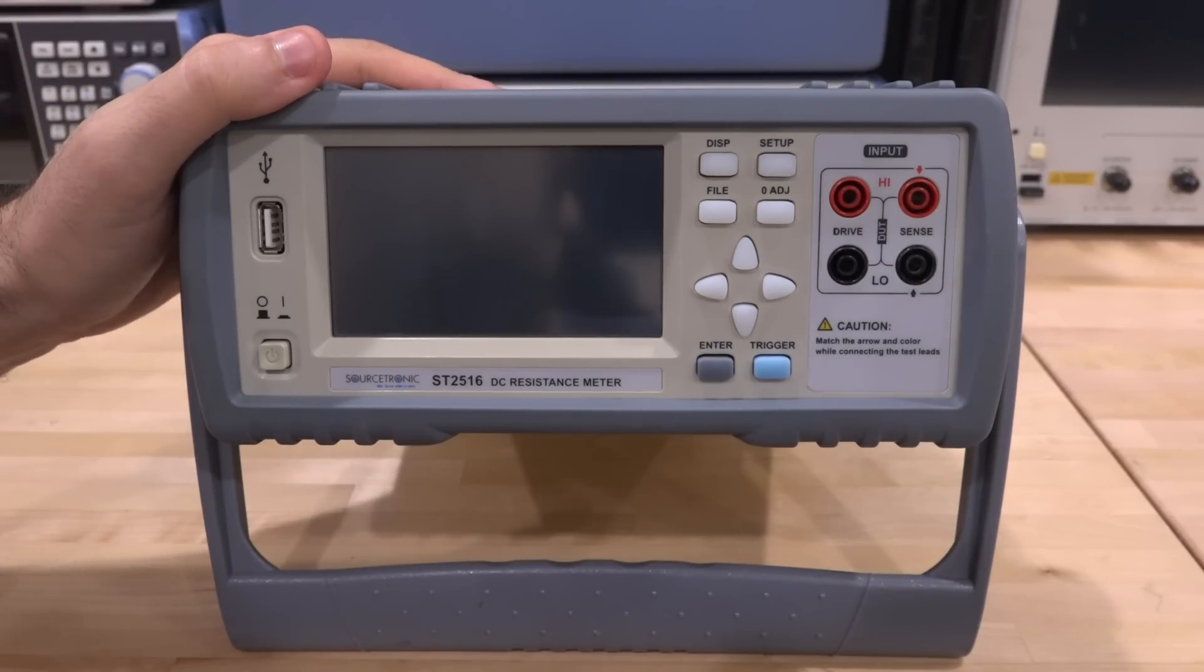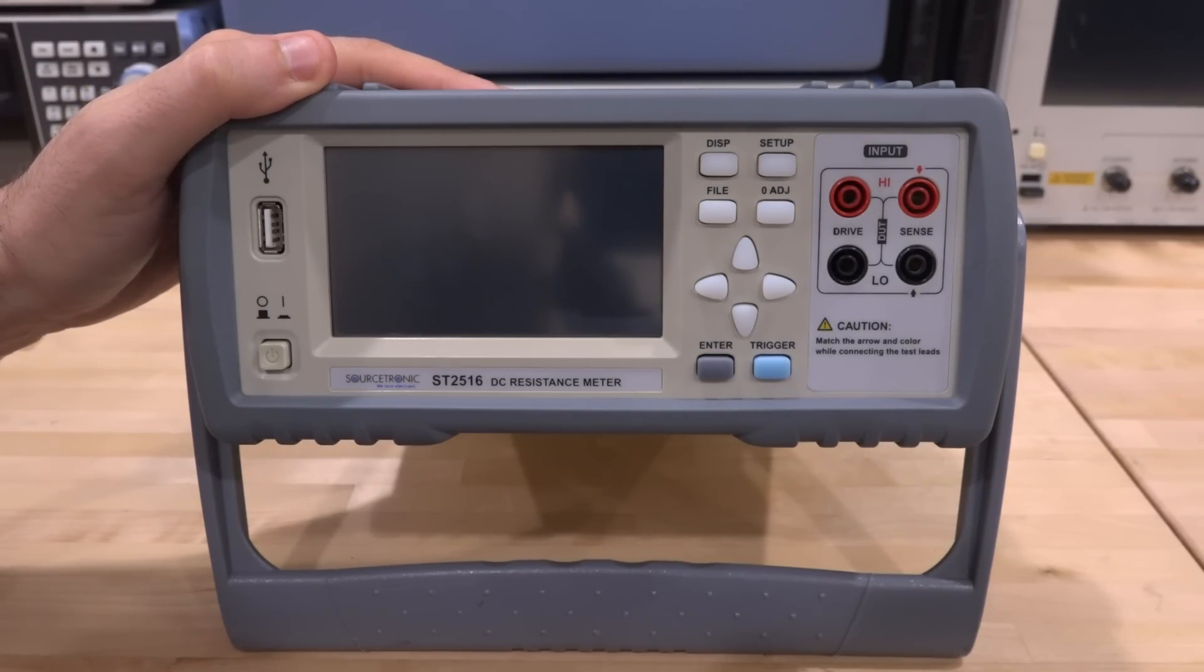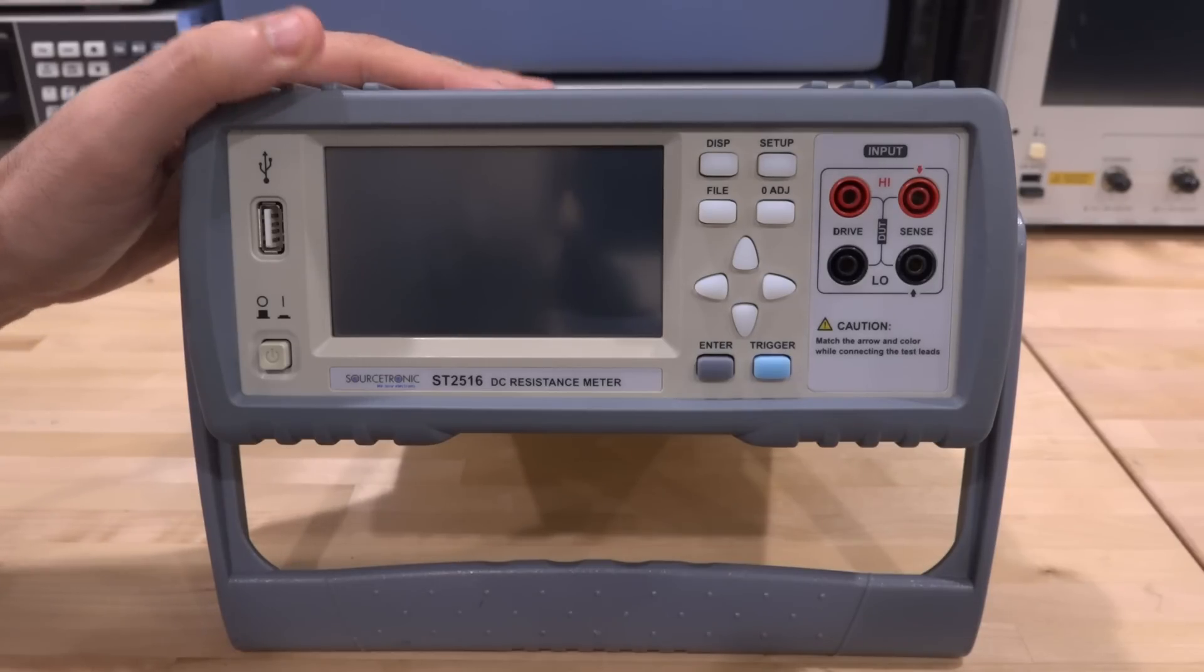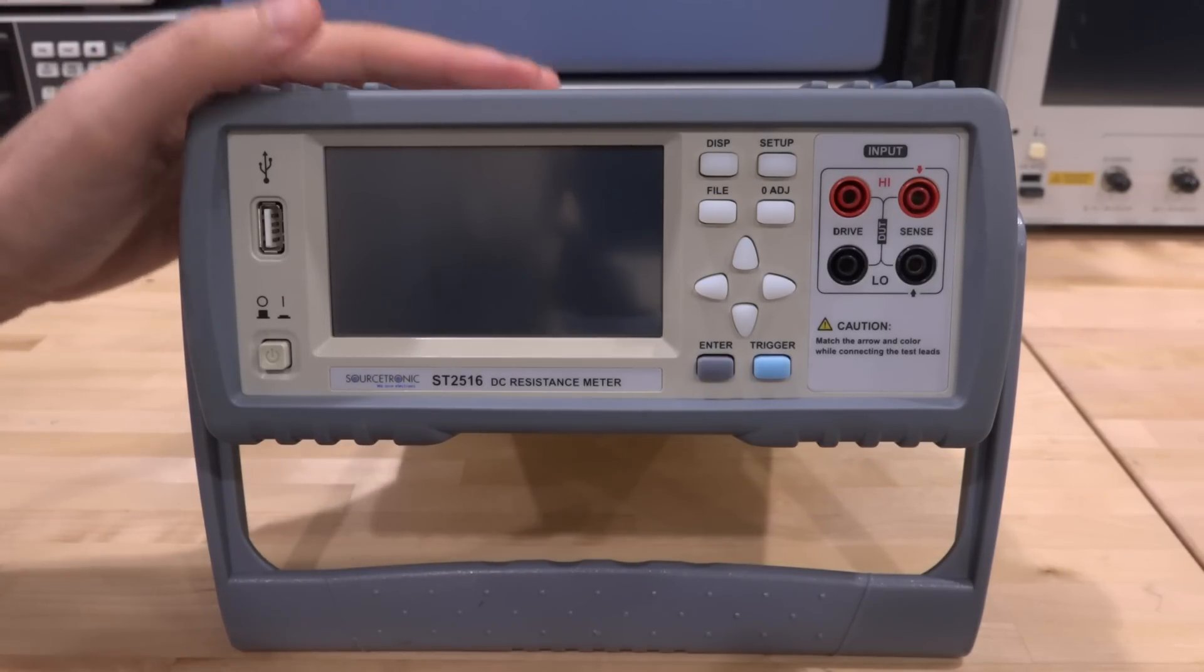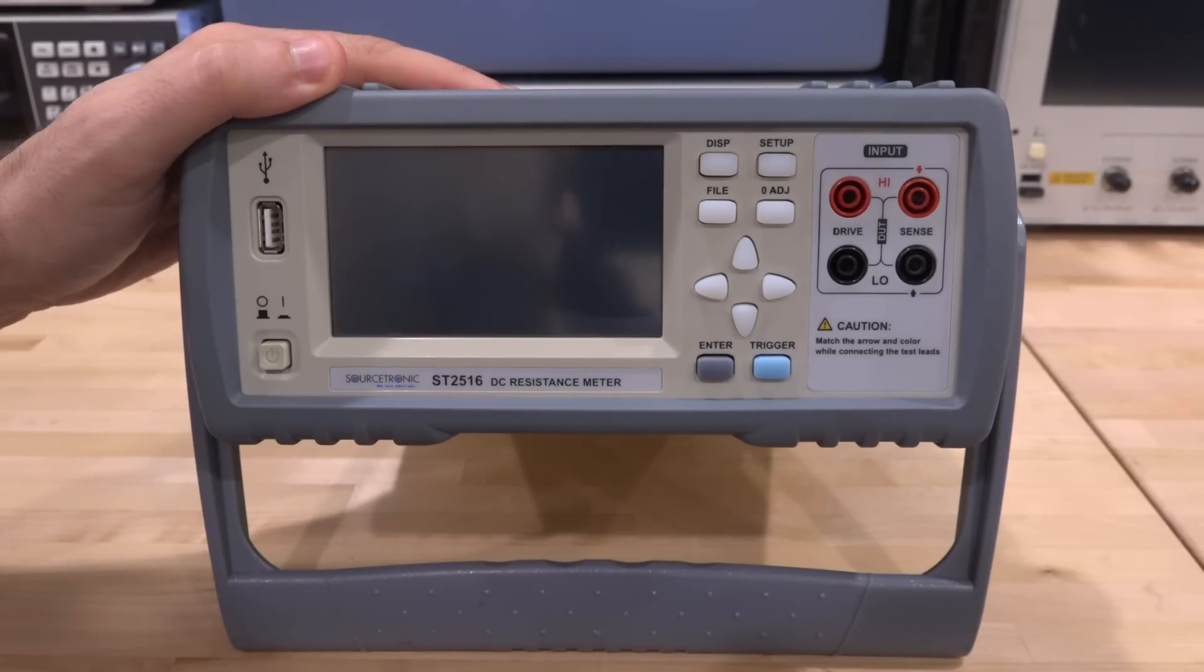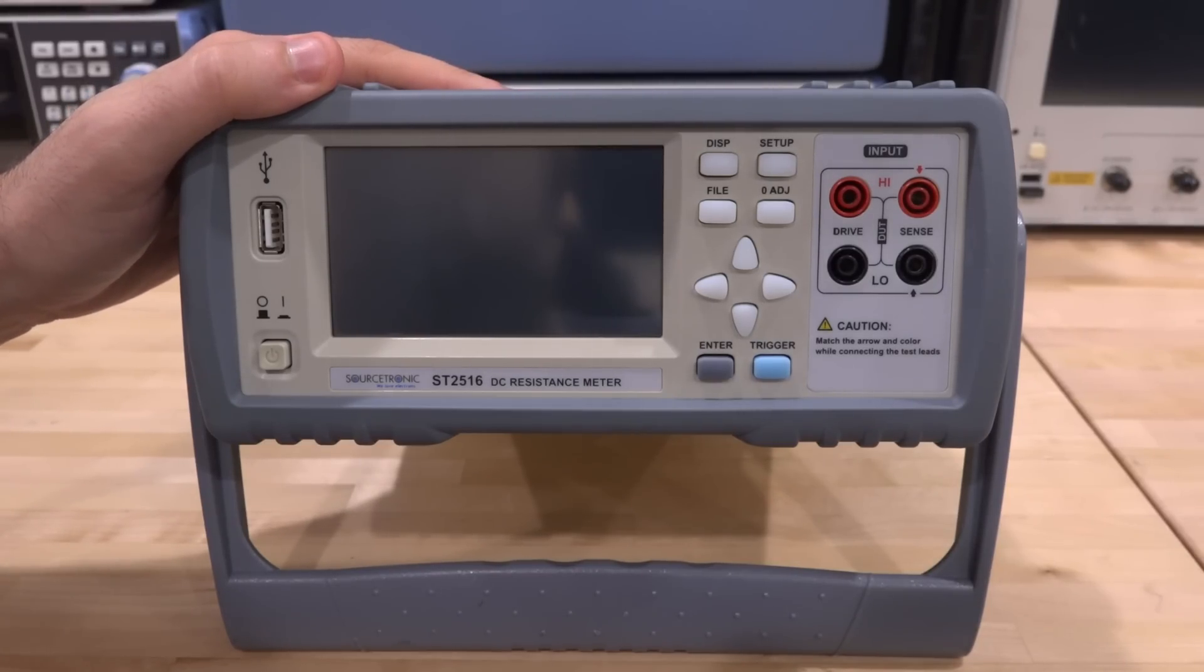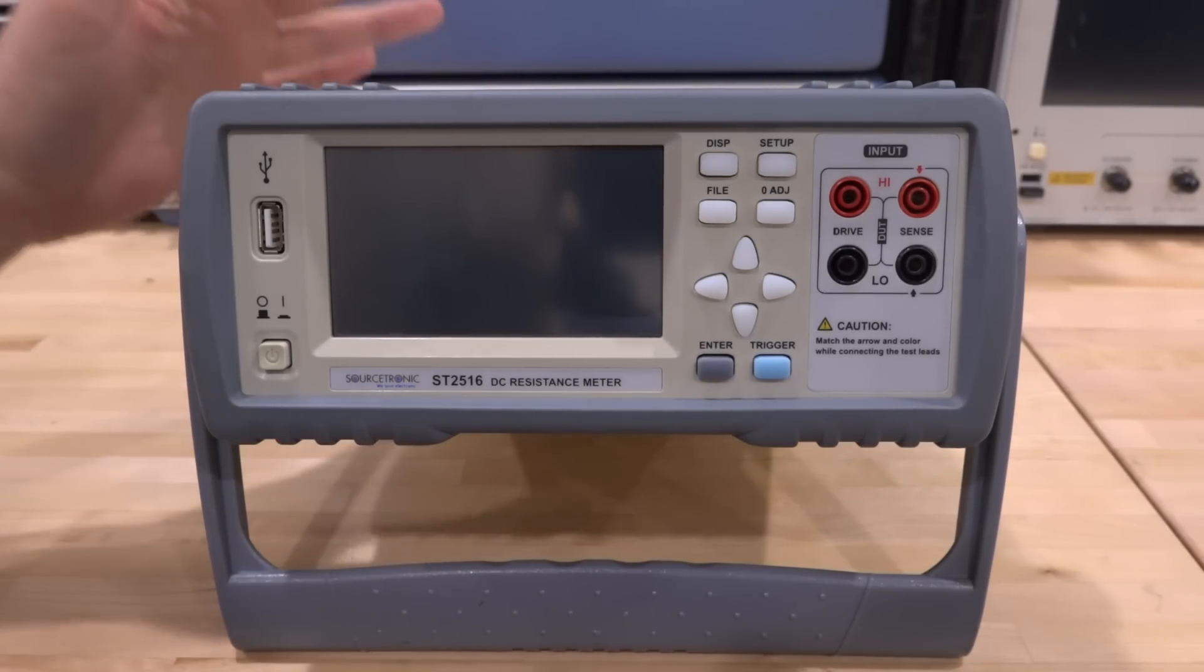Now the DC resistance meter like this uses Ohm's law essentially. It's very different than some of the other units that I have that measure also very small resistances, and this thing can put out up to an amp and because of that it has a resolution of one micro ohm. So you can measure really tiny resistances, very useful around the lab.